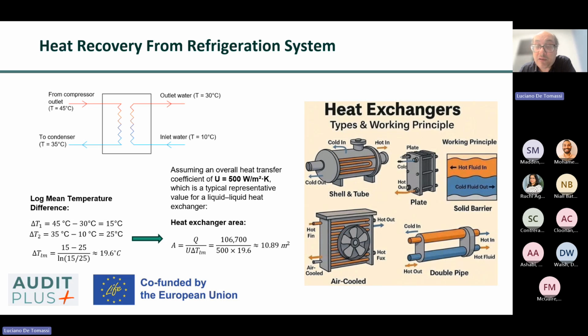The LMTD method accounts for the fact that the temperature difference between the refrigerant and the heating water changes along the length of the exchanger. It is calculated using the inlet and outlet temperature differences between the two streams, providing an average driving force for the heat transfer. A closer temperature approach between the inlet and outlet temperatures of the fluids increases efficiency, but requires a larger heat exchanger area. Conversely, a large temperature difference reduces the exchanger size, but limits the heat recovery efficiency.